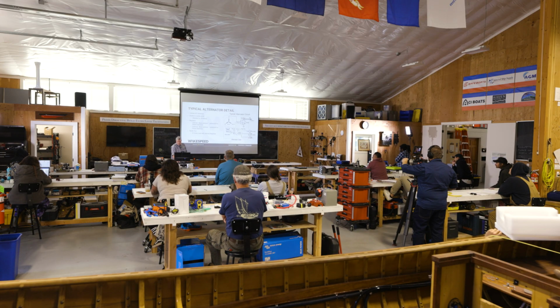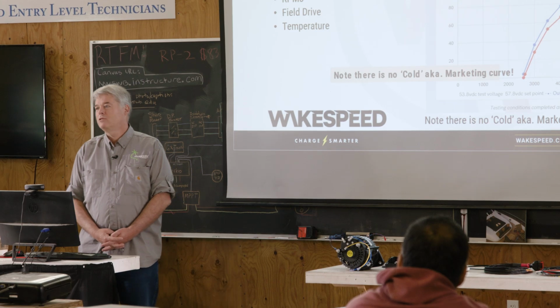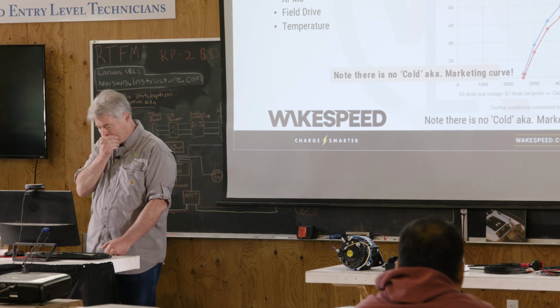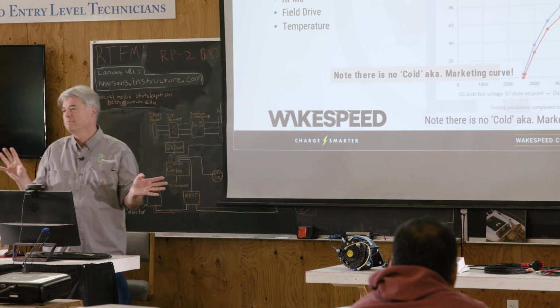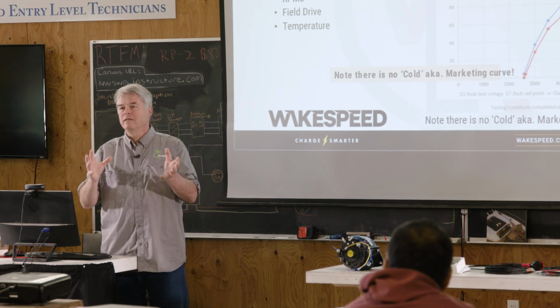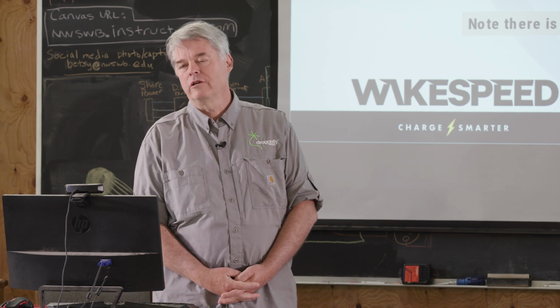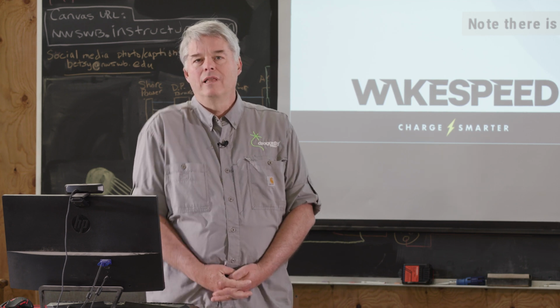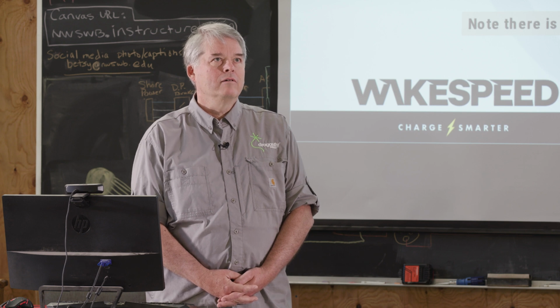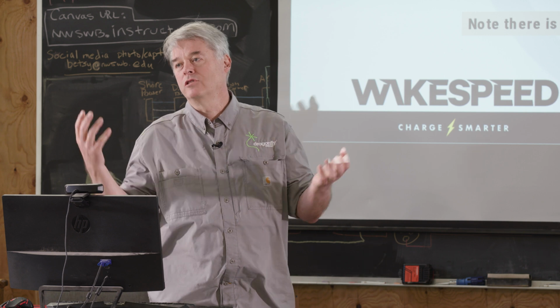One very critical aspect of alternators that I want to talk about is the data sheets. We talked about the data sheets before, right? You have to understand what data is being presented on the alternator. Most alternators will be sold as voltage and current. That current delivered will either be obtained only at a high point or never realistically attainable.